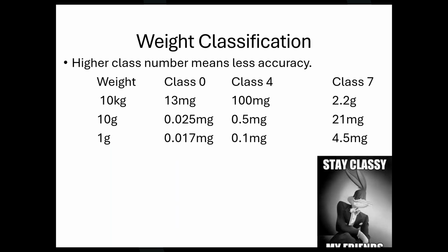What just happened to that weight? It got lighter. You changed it, guys. Or you'll see they'll put a metal tag on it. All right, on one that's 2.2 grams, that metal tag, you can write on it with a Sharpie. It ain't going to matter with that. But when you get down to, where you've got what, 0.013 gram tolerance, when you start etching that thing or you put your little metal ID tag on there, guys, you just ruined your $1,900 weight, because it ain't no good at that point. So you can see as we go out here what the differences are in this.